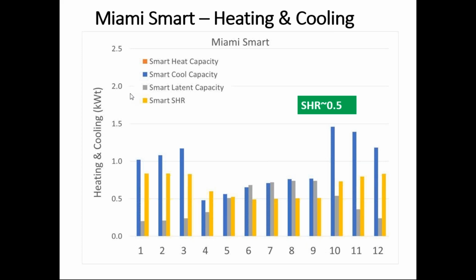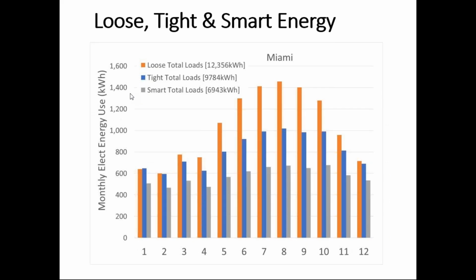But again, looking at that daily capacity chart, most likely you would want to have a dehumidifier in addition to the standard cooling heat pump. But stage it so that it is not always running, because with today's modern variable speed drive heat pumps you get higher efficiency, which will give you a higher energy factor than a dehumidifier.